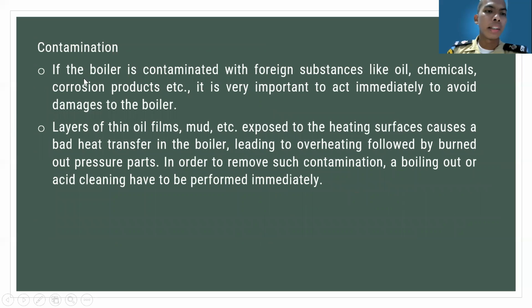And this is the contamination. If the boiler is contaminated with foreign substances like oil, chemicals, corrosion products, etc., it is very important to act immediately to avoid damage to the boiler. And also layers of scale, oil films, mud, etc., on the heating surface cause bad heat transfer in the boiler, leading to overheating, followed by burnout of pressure parts. In order to remove such contamination, a boiling out or acid cleaning has to be performed immediately.